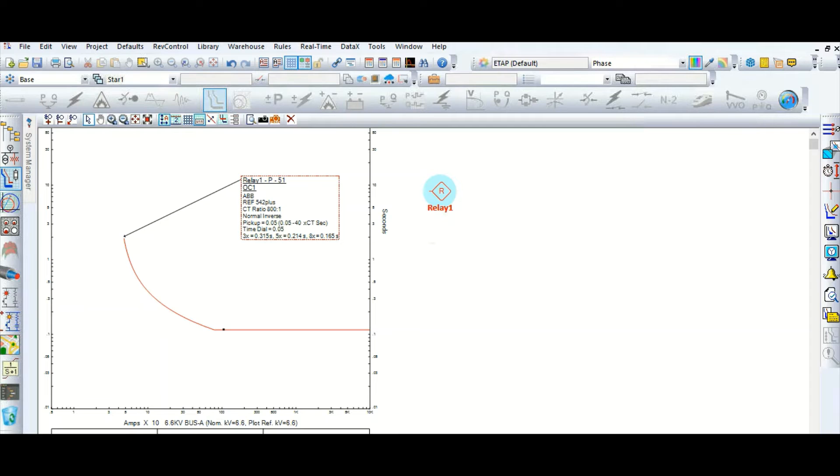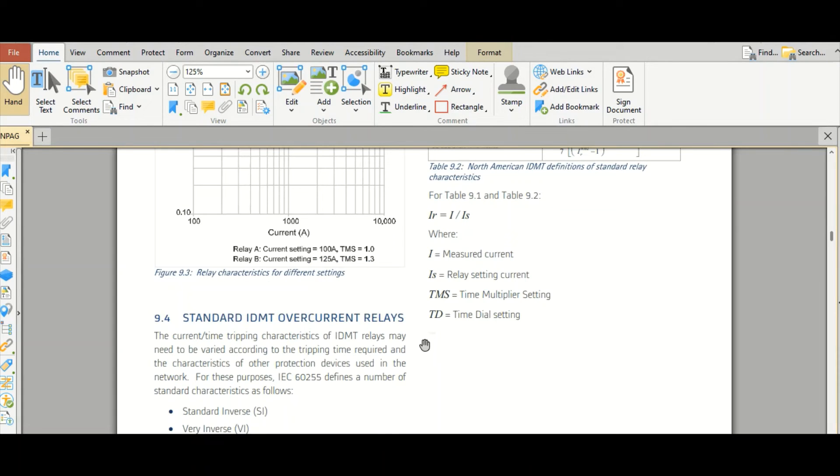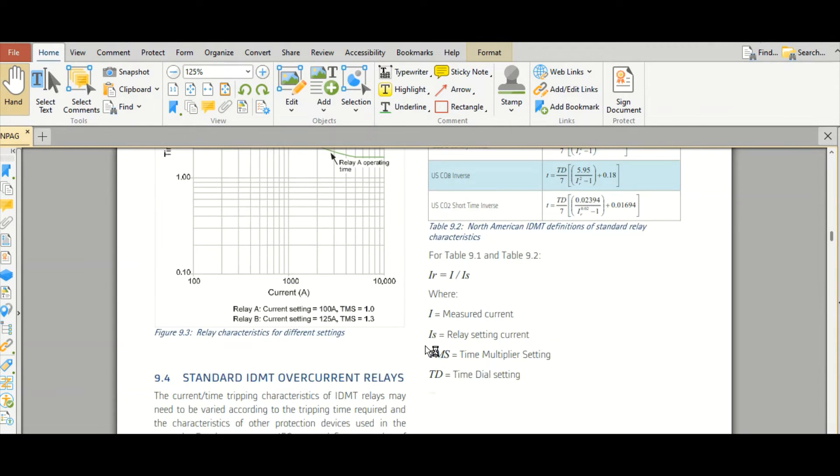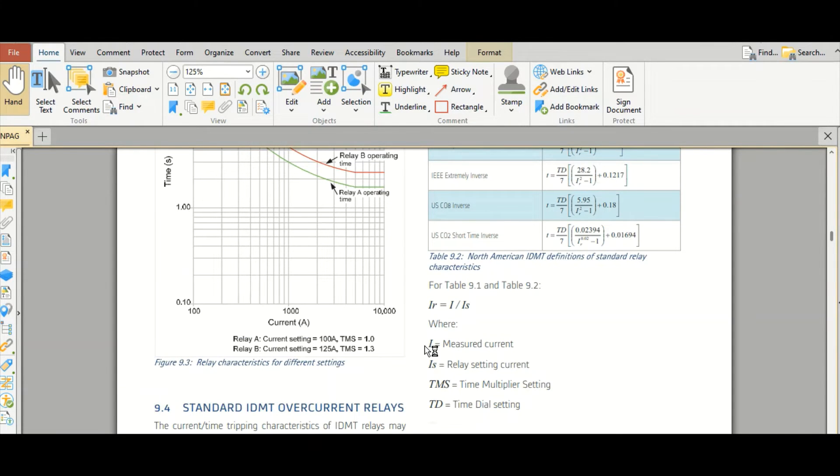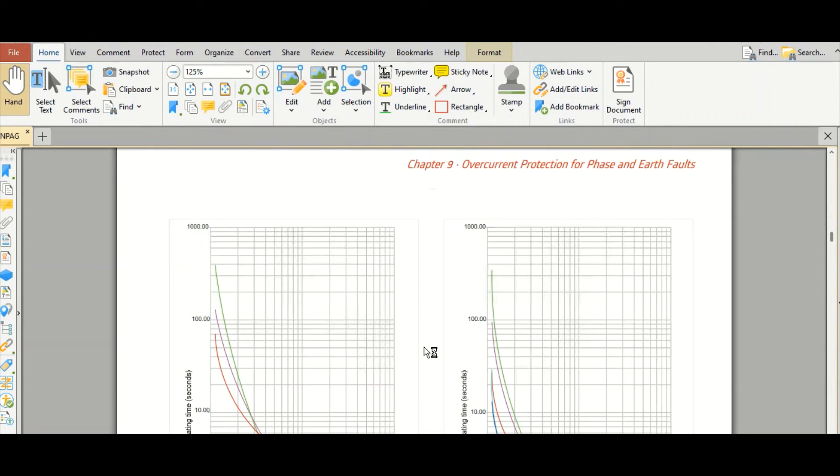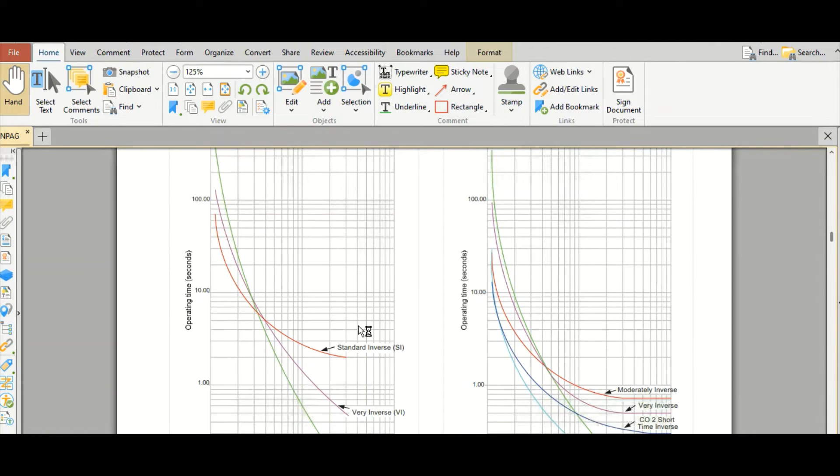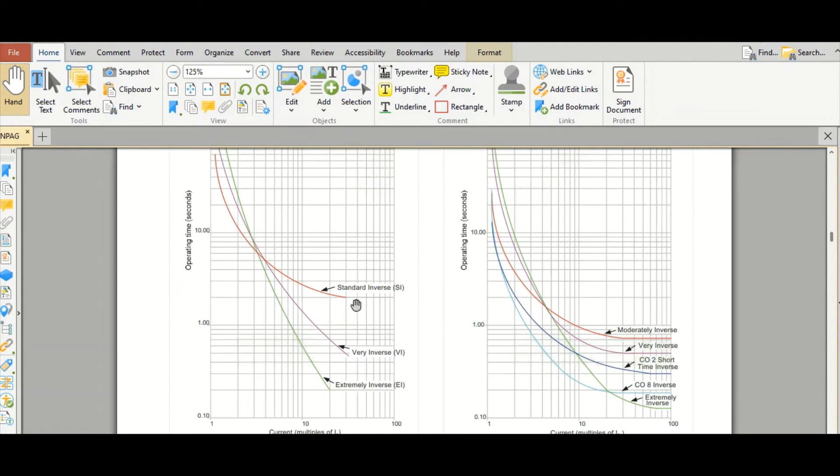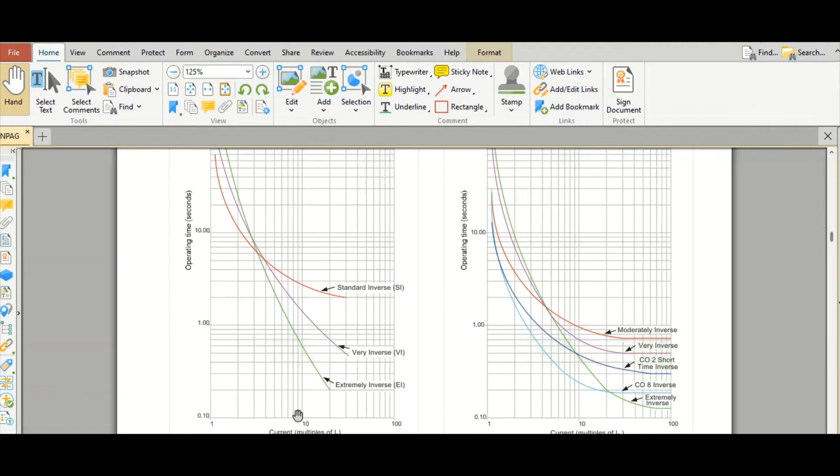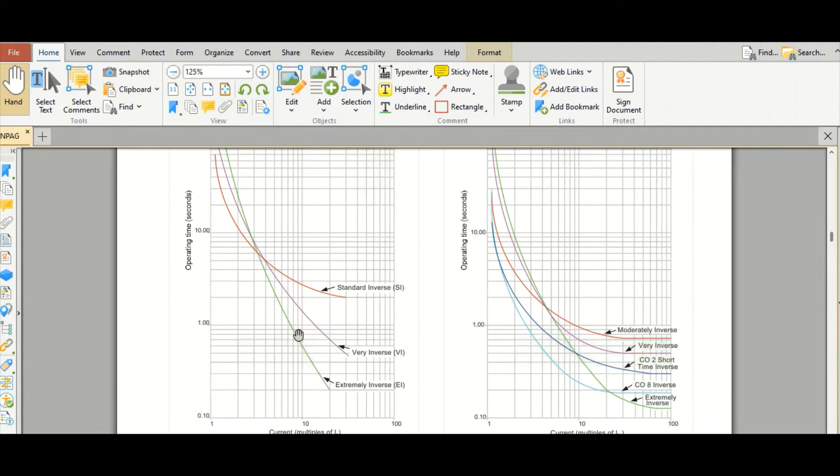If you see in the manual here, let's say I will show you something, what is the difference between this. So as you can see, this is the standard inverse curve. This is operating time on Y-axis and X-axis is current. So time current characteristic curve, which is called TCC curve. Here, this red color, this is standard inverse curve, IDMT standard inverse. This is very inverse, this is very inverse characteristic. And this is extremely inverse. So standard inverse or normal inverse, very inverse, and extremely inverse.